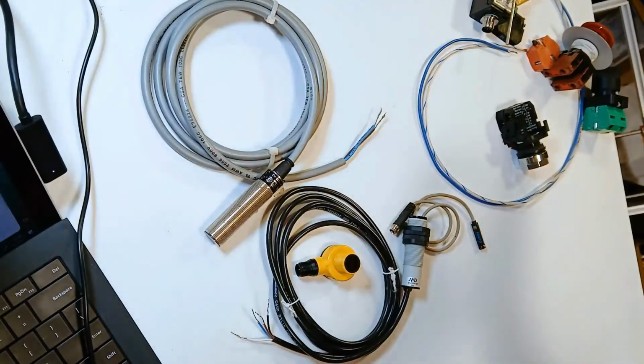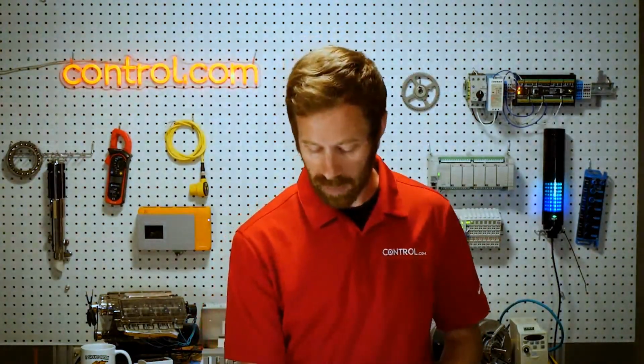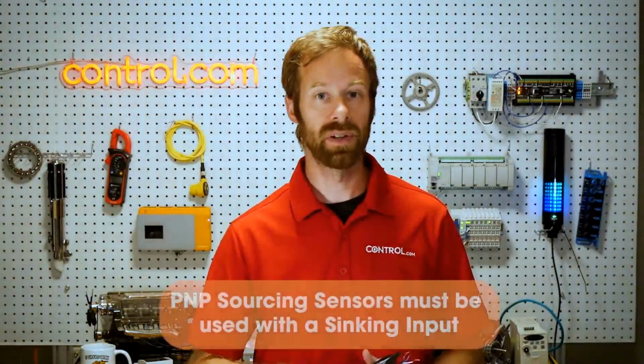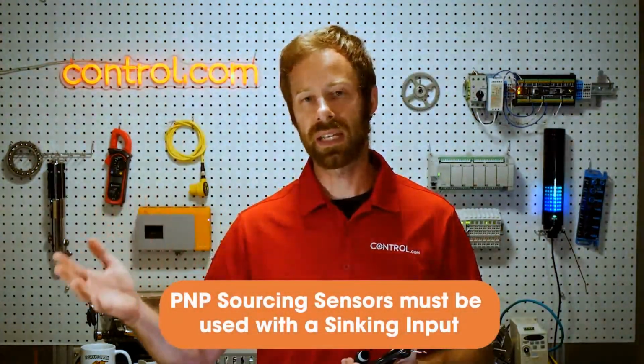Also, the mechanical switches were non-polar. You could apply electricity in either direction and it was fine. But with a three-wire sensor, we have to be careful to look at the NPN or PNP output to make sure that it's compatible with the control system. Quick hint here is if we have a PNP sourcing sensor, that's got to be used with a sinking input.